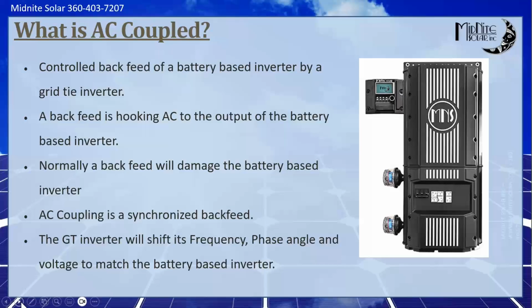If you could watch it on an oscilloscope, you would see that the Rosie will move its sine wave back and forth a little bit and up and down a little bit until it locks to the other inverter. Actually, I'm sorry, the grid tie inverter will move its sine wave around to match the Rosie, and when the two match, they lock together. It's the same thing the Rosie does when it connects to the utility grid, or any battery-based inverter when it connects to the utility grid. So it'll synchronize, then it will lock, and then it will ramp slowly, and that's where we get the fact that it's okay to do. And again, the GT inverter, GT standing for grid tie in this case, will actually shift its phase angle and everything to lock. It's kind of fun to watch happen in real time, and it does work very, very well.